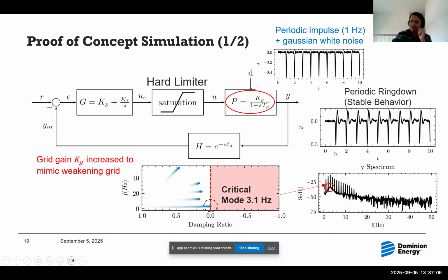While we're in the stable period, while the controller is stable, the grid is in stable conditions. If we plot the power spectral density of this output, on the bottom right, you'll see the effects of the periodic impulse as spikes in the spectrum every 1 hertz, and also the critical mode dynamics at 3.1 hertz, seen as a hump. So a thing to think about is that there's a combination of inputs and the autonomous response of the grid to the inputs, and it's very important to distinguish between the two. These are not two additive dynamics - one is driving the other. It's important to keep that in mind.